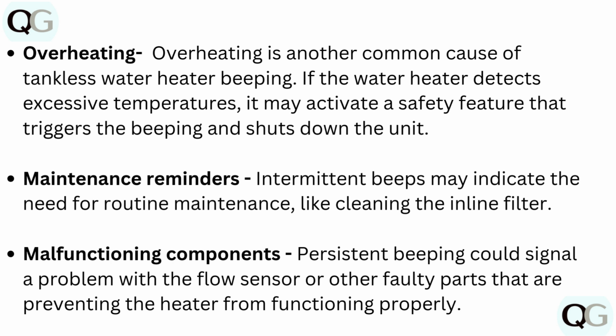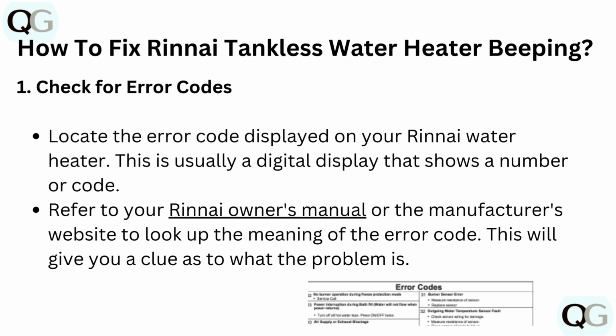Overheating. Overheating is another common cause of tankless water heater beeping. If the water heater detects excessive temperatures, it may activate a safety feature that triggers the beeping and shuts down the unit. Maintenance reminders. Intermittent beeps may indicate the need for routine maintenance, like cleaning the inline filter. Malfunctioning components. Persistent beeping could signal a problem with the flow sensor or other faulty parts that are preventing the heater from functioning properly. How to fix Rinnai Tankless Water Heater beeping.